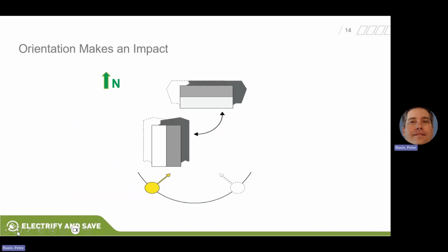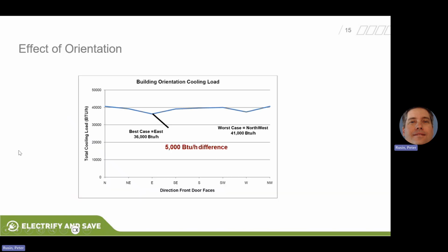Orientation does make an impact. Yes, orientation matters because of solar heat gain—not as much in northern Wyoming, but especially in Colorado and New Mexico, where we have huge solar impacts. Here's an example: this is a small home, and depending on whether it's oriented from the east side versus northwest, there can be a 5,000 BTU or a half ton difference in that sizing calculation. I'm not saying every house will have a half ton difference—you really need to study it, because there could be shading or trees—but in an open area there are differences based on orientation that you should take into account.